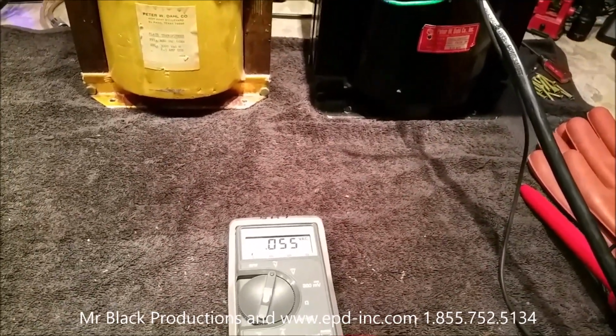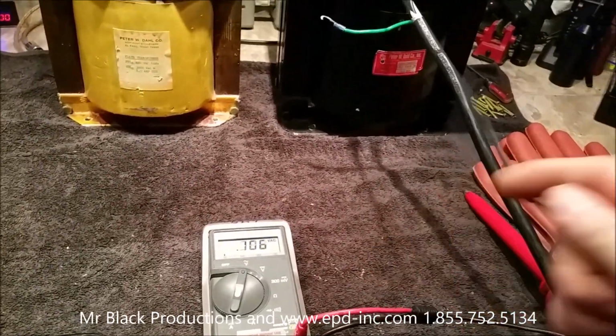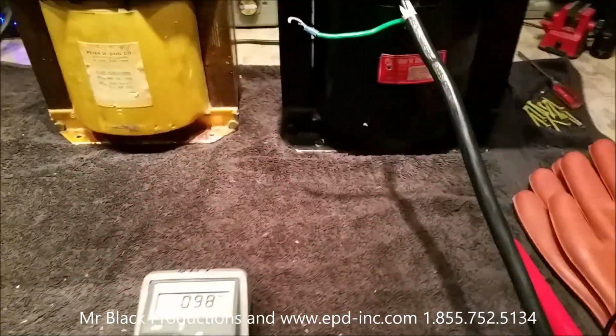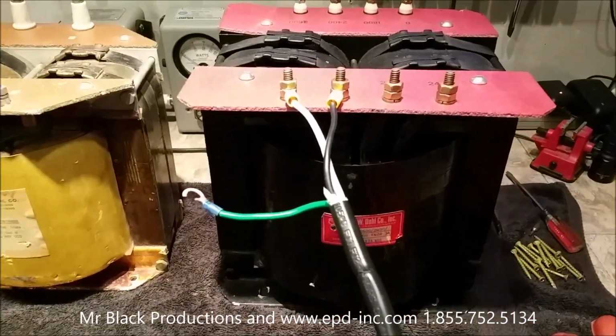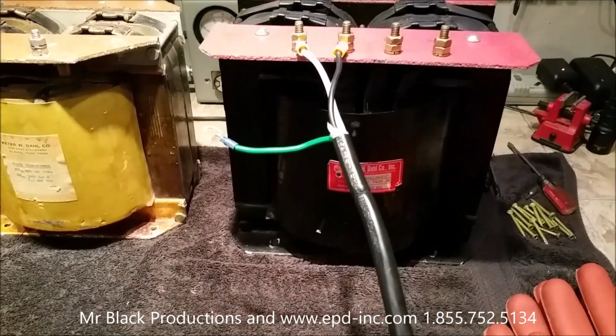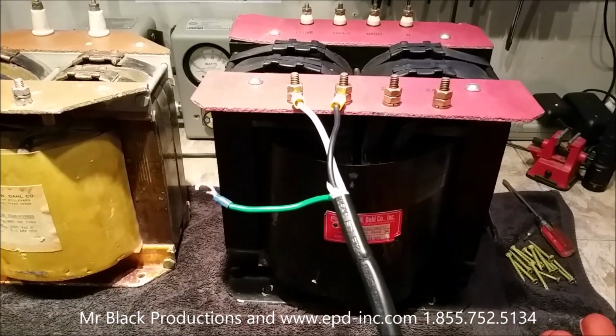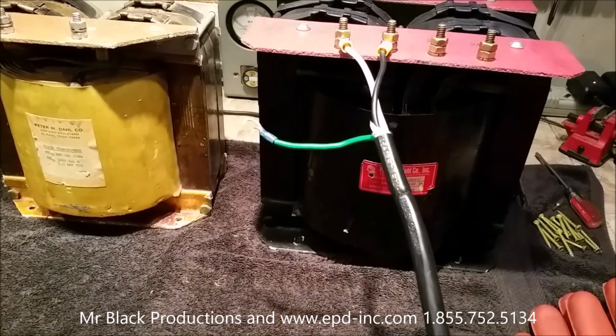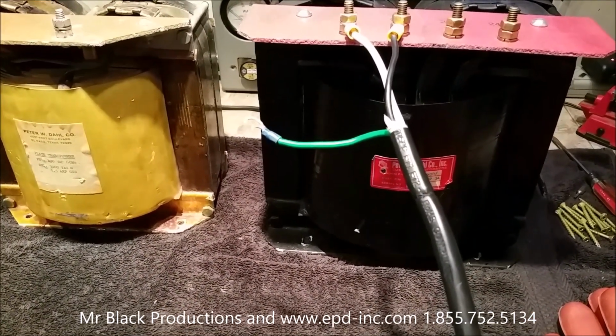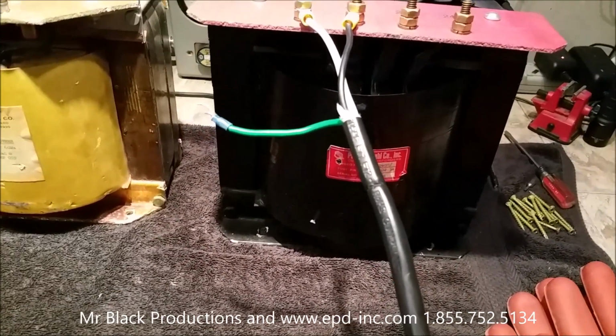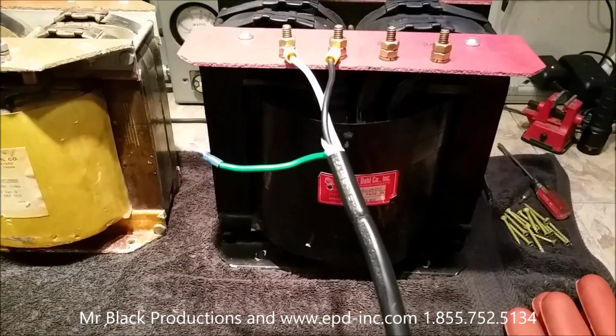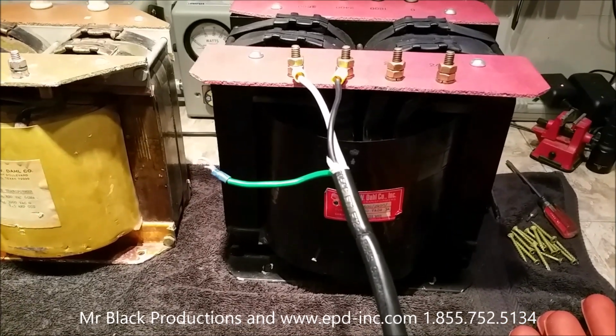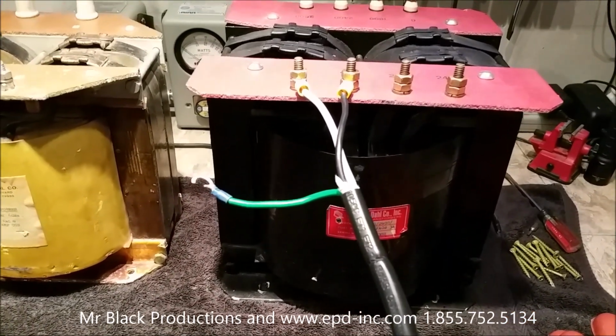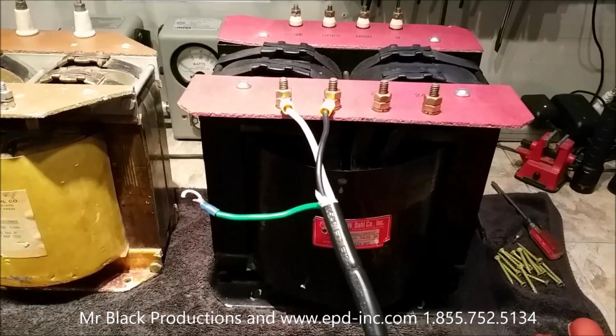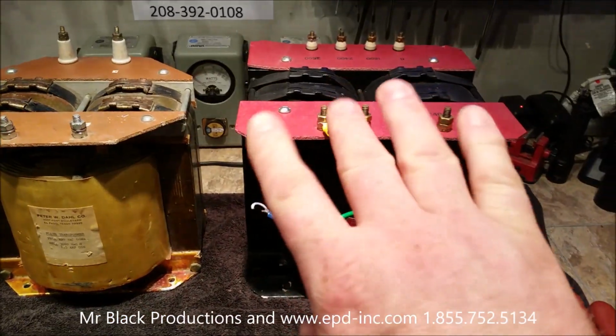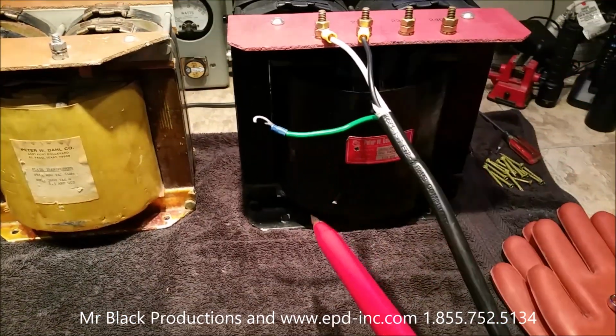I had a gentleman call me once and say, hey, I got this new transformer, and every time I hook it up it pops a breaker. I asked how he had it wired. He said, I've got the green wire going to 0, the white wire going to 220, and the black wire going to 230 — that puts me on the 230 tap, right? All I could do was start chuckling. I said nope. What he'd actually done was short all three terminals together by attaching the ground lead wrong.